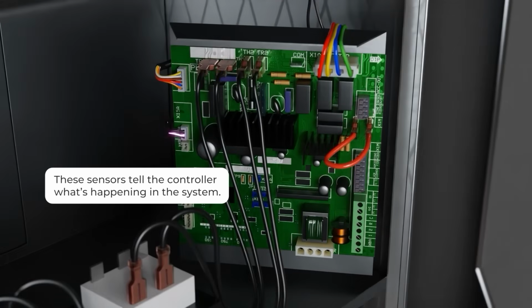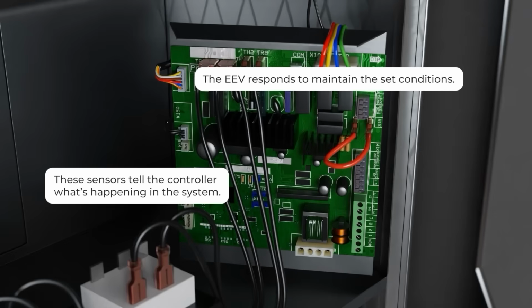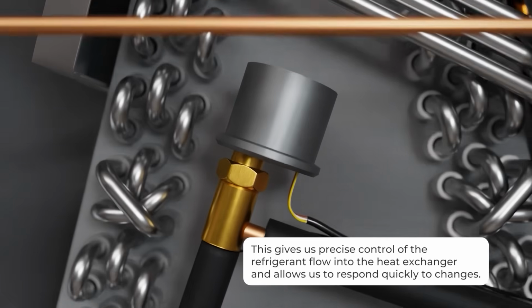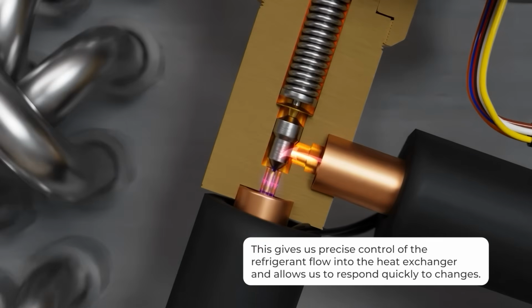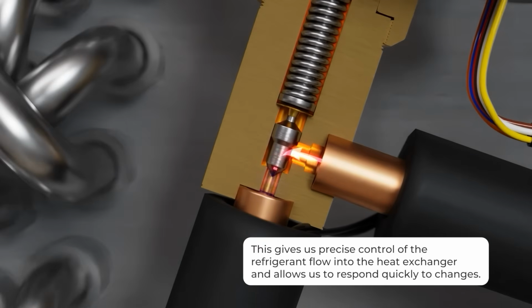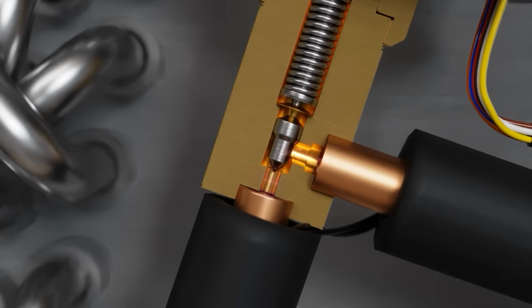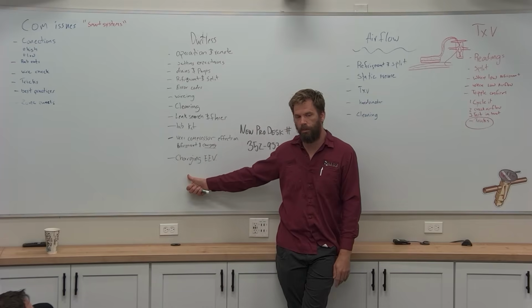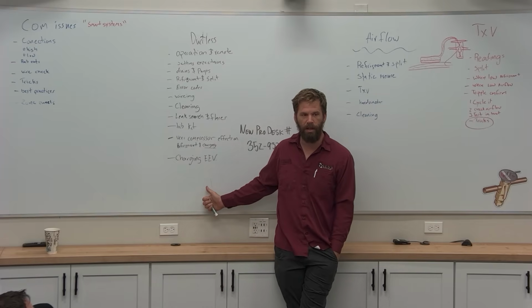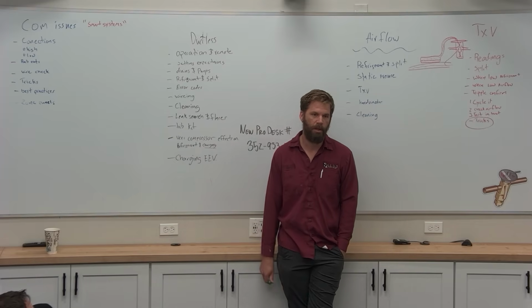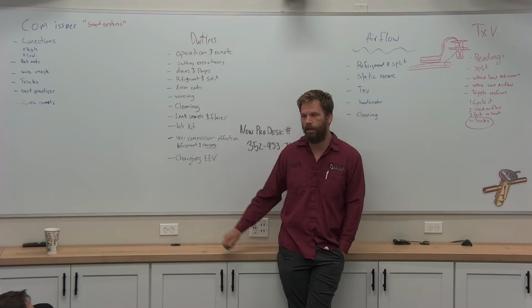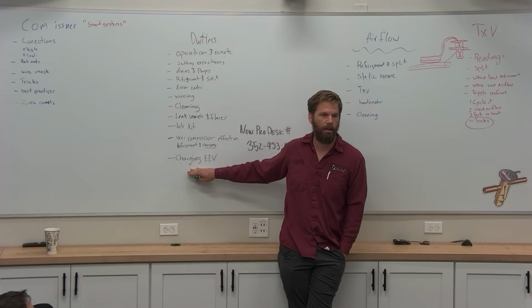Then you have to stop, let it circulate through the whole system, let that line come back to a normal pressure, normal temperature, run for a few minutes, let that thing settle somewhere to know if you need to keep adding or not. When you're adding to a ductless system, you're charging based on superheat. You're not trying to get it up to 40 saturation, you're trying to get your superheat down below 9 degrees typically. And so it can be as low as 2 degrees superheat, and that's totally normal for a ductless.